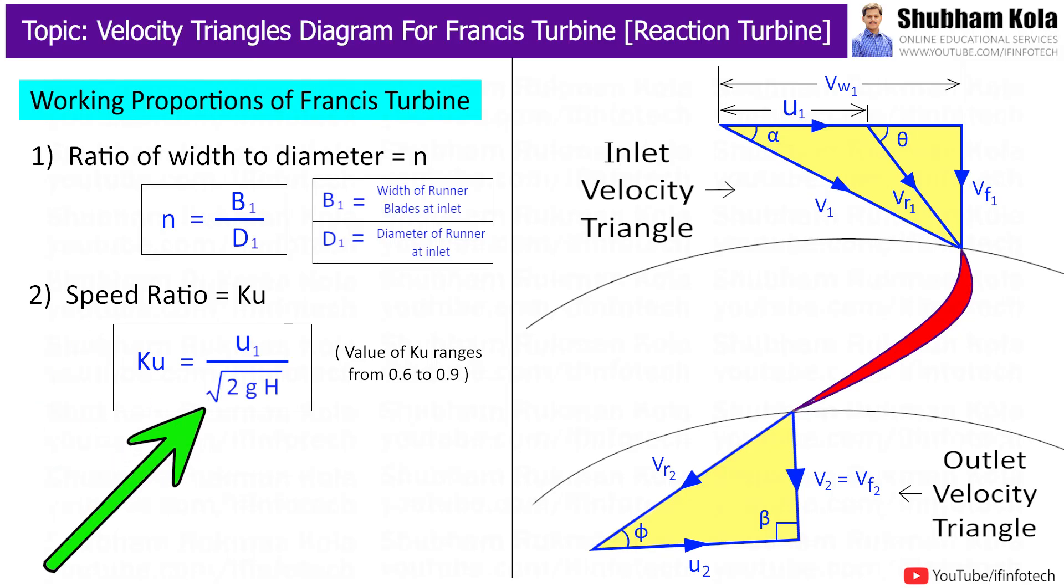The speed ratio is the ratio of tangential velocity at inlet to the theoretical jet velocity called as spouting velocity i.e. square root of 2gH. And the value of speed ratio ranges from 0.6 to 0.9.